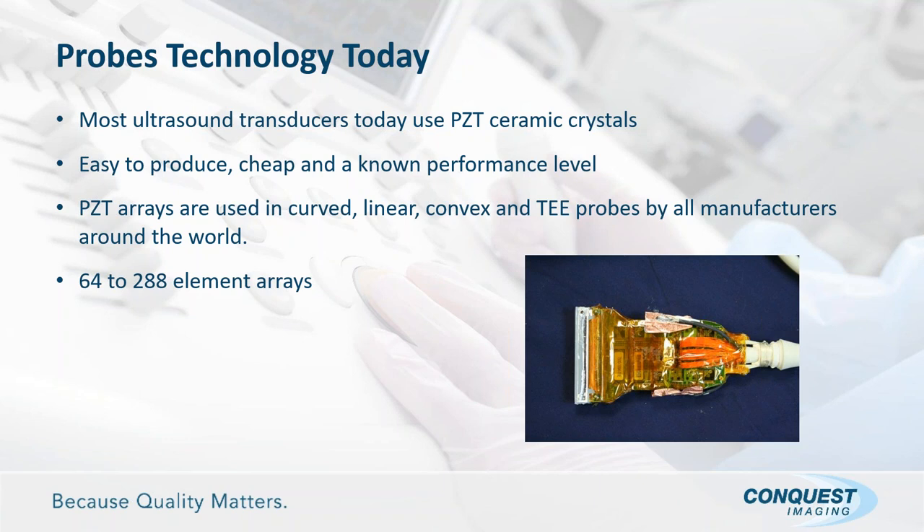Most ultrasound transducers today use a PZT ceramic crystal array — a ceramic compound that has been around for several years. It's a good-performing piezoelectric material, which is why many manufacturers continue to use it. It's relatively easy to produce, raw materials are available, and it has a known performance level. These arrays are used in every type of probe — curved, linear, convex, TEE, etc. New ultrasound system platforms still use PZT-type array probes, and they work just fine.